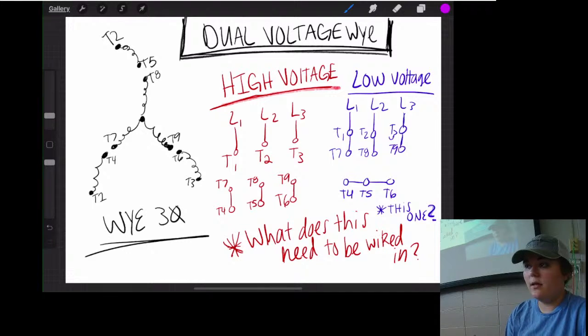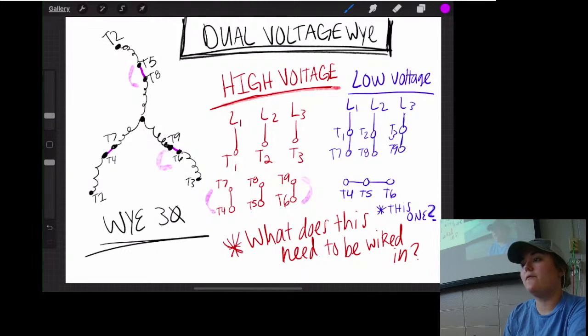So where are we going to connect T5? To T8. T9? To T6. T7? To T4. That diagram tells you that - T7 to T4, T8 to T5, T9 to T6. That's how you would wire up a dual voltage Y three-phase motor for high voltage - you need it in series, so literally all of this is connected.